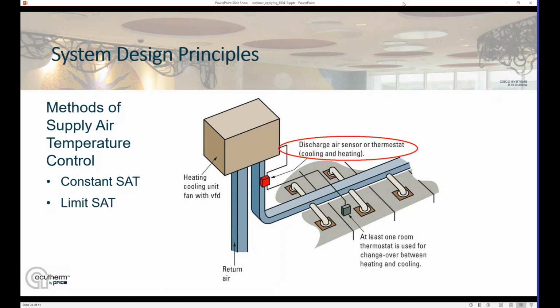If you're working with older systems, retrofit situations, at a minimum, you want to make sure you have a cooling low limit just to make sure that the air doesn't get too cold, and a heating high limit, to make sure it doesn't get too hot. Working with the bypass and the pressure control, we don't want that cold air looping back around and freezing the coil, or the hot air tripping the unit on high heat. So you do need some kind of limitation on there at a minimum, but if you can get that modulating unit on there, all the better, for better control, better comfort, and really better energy savings.